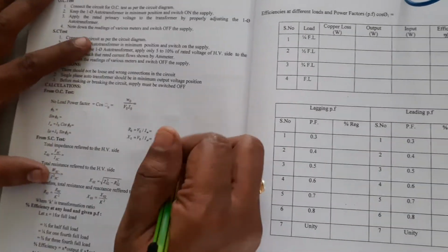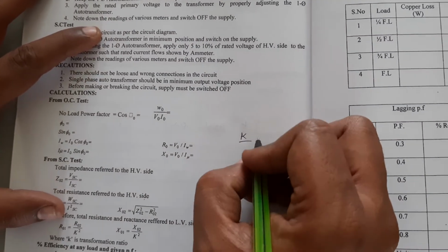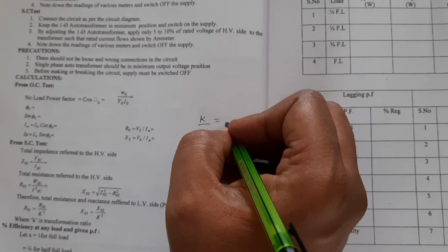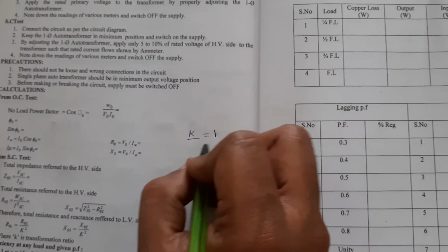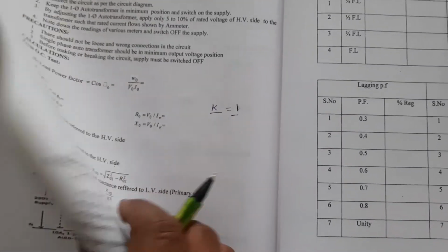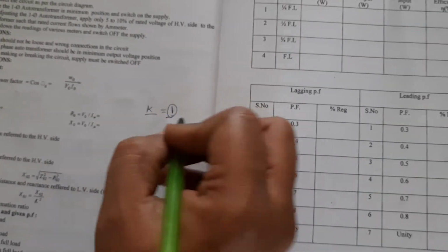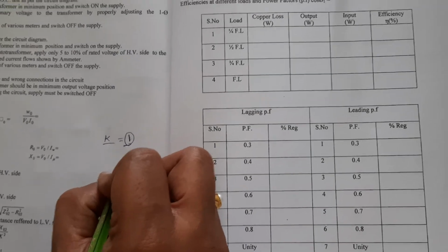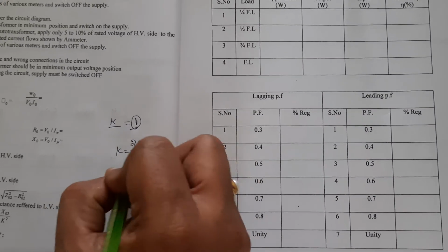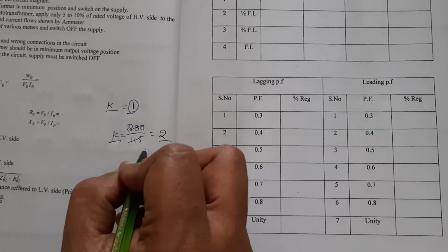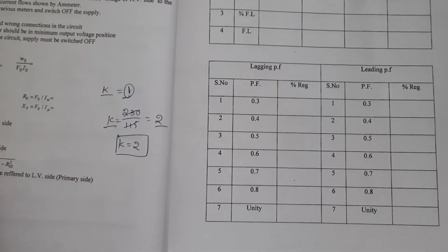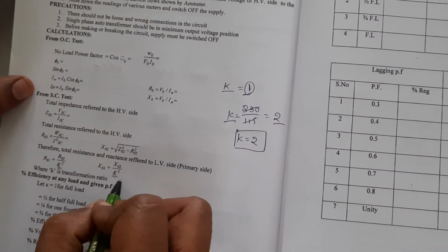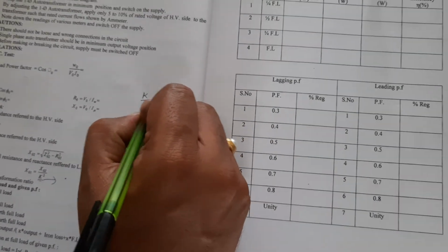After these readings, we have to do all the calculations from the OC test and SC test. And always remember, the multiplication factor or transformer ratio is generally taken as 1. But here we have taken a single phase transformer with ratio 230 by 115 volts, so we get 2. The transformer ratio is 2, K is equal to 2. You have to consider this transformer ratio as 2 whenever you multiply. Generally it will be 1 for a normal transformer, but here we have a step up transformer.